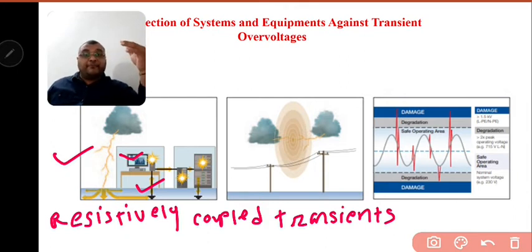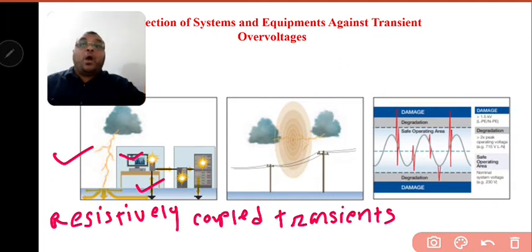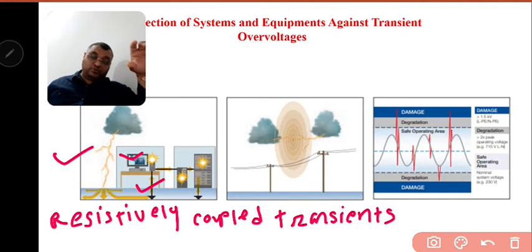Energy from ground strikes flows away through the path of least resistance and increases the potential in local earths, cabling, and electronic circuitry. Where these are linked to separate earths by a metallic service line, the potential is shared, creating transient over voltages as the current attempts to flow. Whenever it finds the lowest resistance part, it passes through that way - this is known as the resistively coupled transient.